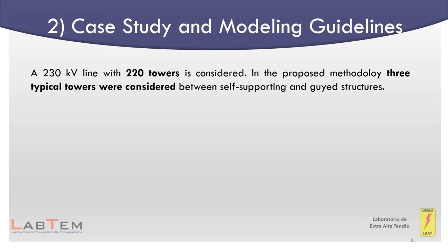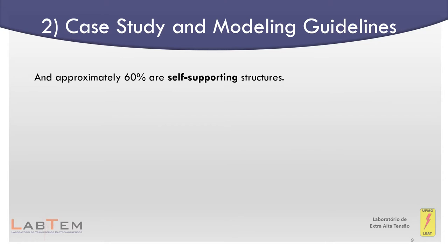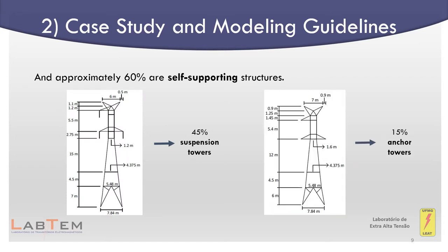A 230 kV line with 220 towers is considered in simulations. In the proposed methodology, three typical towers were considered between self-supporting and guyed structures, of which about 40% are guyed towers and approximately 60% are self-supporting structures, which are about 45% suspension towers and 15% anchor towers. All simulations presented in this paper have been carried out in the Alternative Transients Program, ATP.